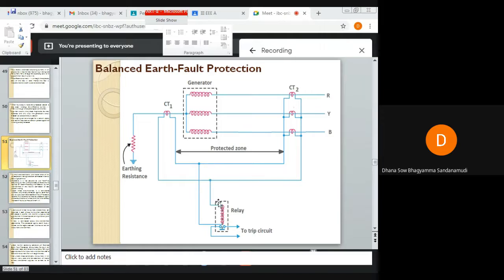So the differential current flowing through the relay will be zero when the current in the secondary of this CT1 is equal and opposite to the algebraic sum of the secondaries of all these three CT2s of all three phases. If this is I1, it will be equal to IR plus IY plus IB. When I1 is equal to IR plus IY plus IB, equal and opposite, the resultant or differential current will be equal to 0. So no current will flow through the relay and the relay will not operate. We can say that the current in this neutral wire is 0, and the secondary of the neutral current transformer supplies no current to the relay. That is under normal operating condition.